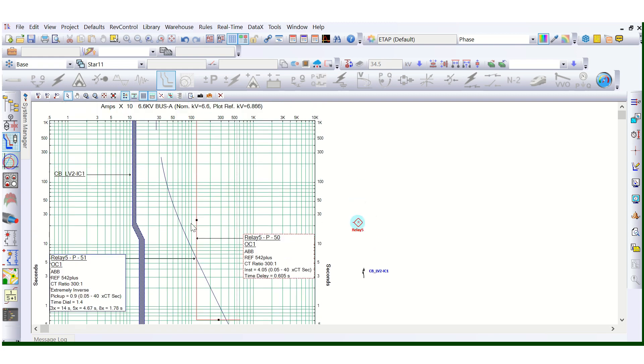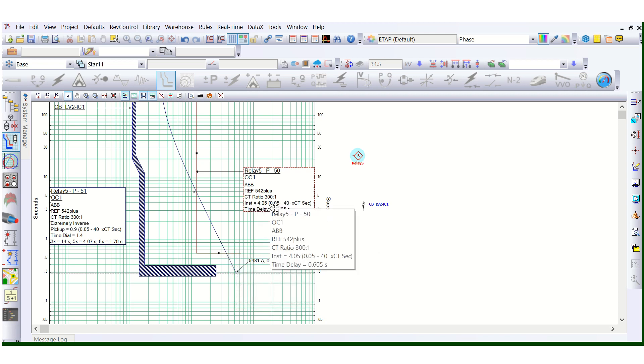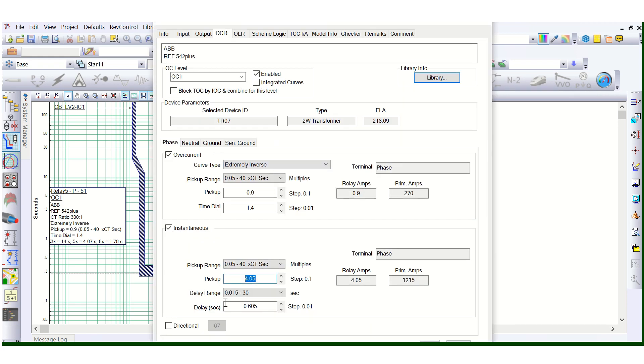This time delay is 0.605 seconds — approximately 0.6, that means 600 milliseconds, or accurately 605 milliseconds. The instantaneous pickup setting is 4.05. So pickup is 4.05 and time delay is 0.605 seconds.